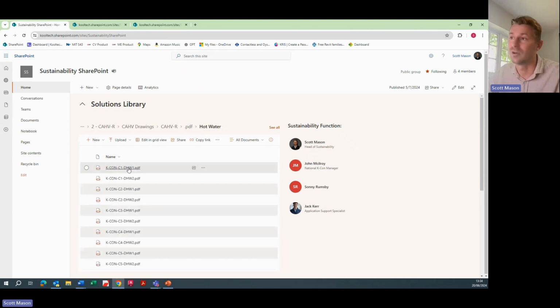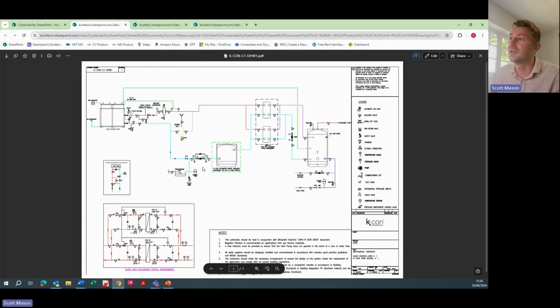Your possible hot water application is going to look something like this. If you went dedicated hot water, it's very similar, but we're serving a plate heat exchanger to produce our potable hot water. That then goes into a hot water tank, and the return, again, is via this volumizer. Now, what's the point in a volumizer, you ask? Well, if this unit is serving hot water and that vessel is very closely sized to the building's peak flow rate, then we could have a load of cold water flood into the hot water tank. And that whole vessel, if it was undersized, could theoretically get down to the mains feed temperature of 10 degrees.